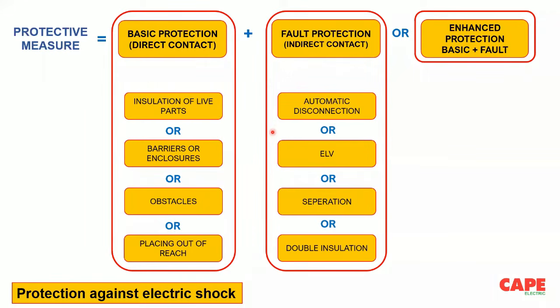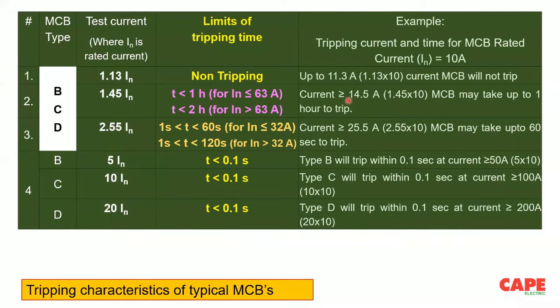Now, when it comes to automatic disconnection, which is one of the safety measures, especially used in AC applications, MCBs are used for automatic disconnection. There are three types of MCBs available: Type B, Type C, Type D. I have put the tripping characteristics of the MCBs. Each of these MCBs has its typical way of disconnection, especially for instantaneous tripping. Type B trips at 3 to 5 times the nominal current, Type C at 5 to 10 times, Type D at 10 to 20 times.